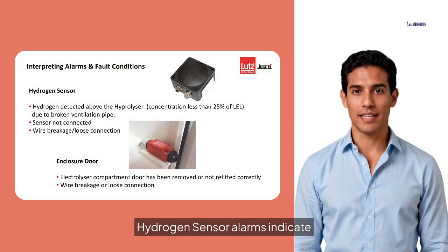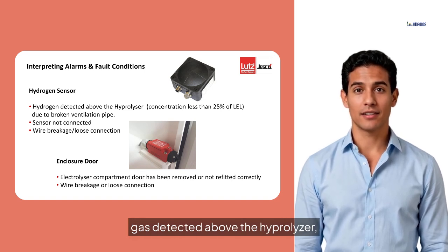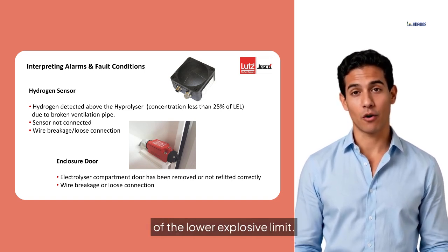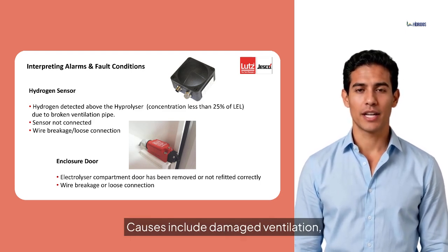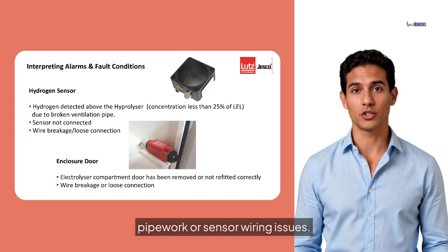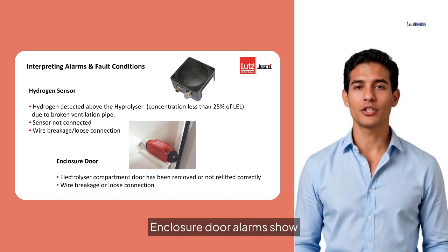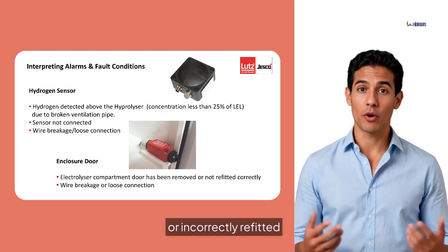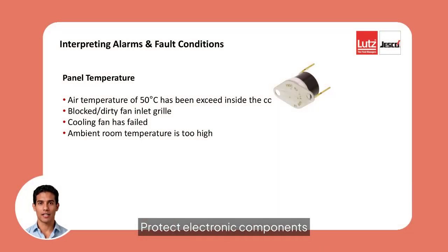Hydrogen sensor alarms indicate gas detected above the Hyprolyser, typically below 25% of the lower explosive limit. Causes include damaged ventilation pipework or sensor wiring issues. Enclosure door alarms show the electrolyzer door is open or incorrectly refitted, or wiring is faulty. Panel temperature alarms protect electronic components. If internal air temperature exceeds 50 degrees Celsius, check for blocked or dirty fan grills, failed cooling fans, or excessive ambient room temperature. Maintaining adequate cooling is essential for long-term system reliability.